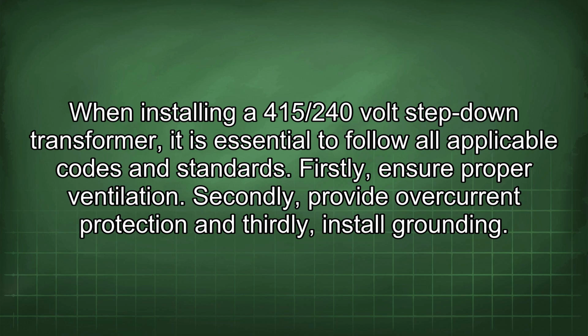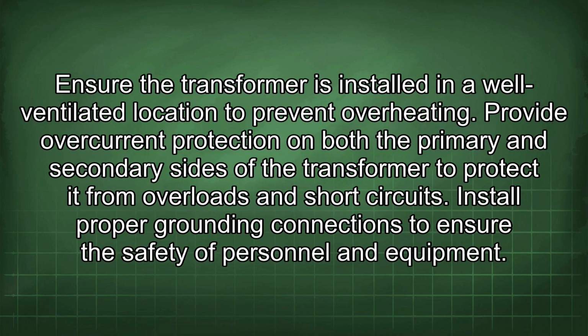When installing a 415/240 volt step-down transformer, it is essential to follow all applicable codes and standards. Firstly, ensure proper ventilation. Secondly, provide overcurrent protection, and thirdly, install grounding. Ensure the transformer is installed in a well-ventilated location to prevent overheating. Provide overcurrent protection on both the primary and secondary sides of the transformer to protect it from overloads and short circuits. Install proper grounding connections to ensure the safety of personnel and equipment.